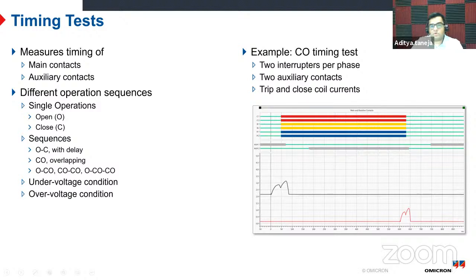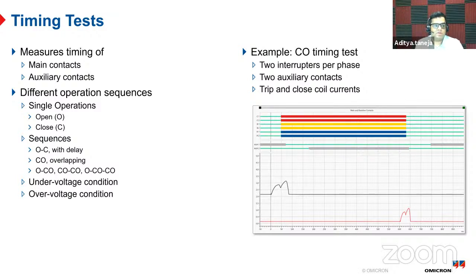And then there are 2 sets of contacts: main contacts and auxiliary contacts. Main contacts have the main work to operate the main currents. Auxiliary contacts, on the other hand, have the work to tell other logic or other parts of the panel, relays and all, that the breaker has operated. So both of them need to be tested.